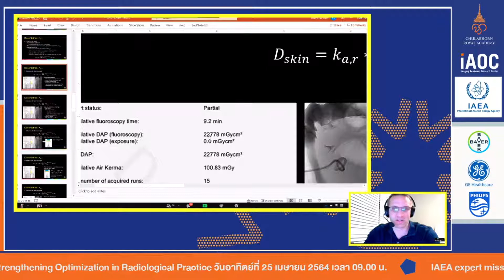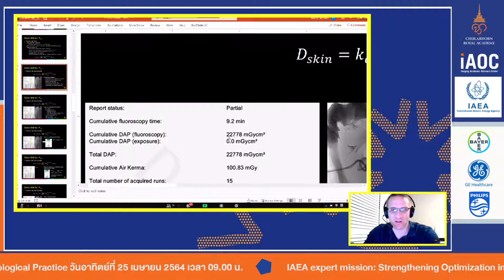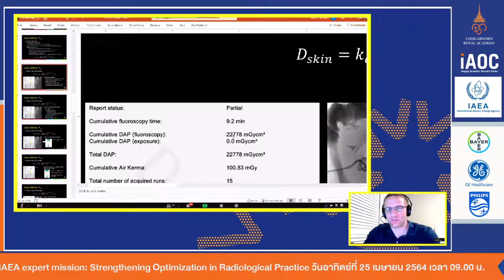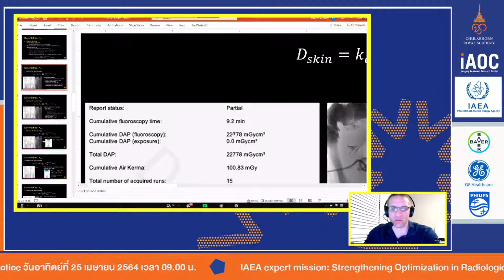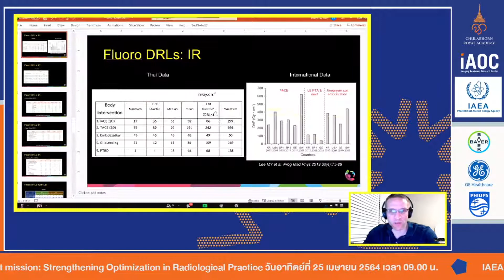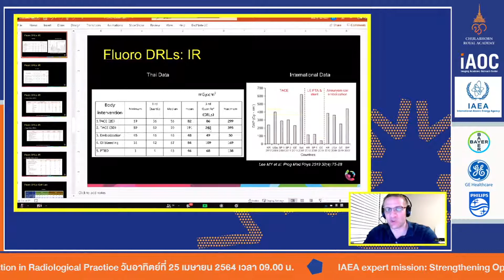Can you see my screen? Is it still presenting? Yes, we can see your screen. So you can see here my cumulative DAP, milligray centimeter squared, is 22,000. So if you move the decimal over 3 for gray, that would be 22.7 gray centimeters squared. And so your numbers were, let me, nope, this one right here. There we go. Milligray centimeter squared, your numbers, I would expect that to be 24,200 or something. I see what you're saying.